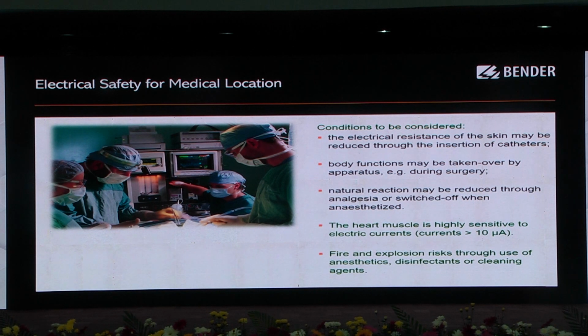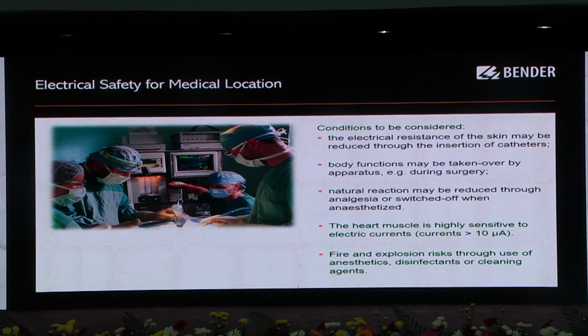it is in the IEC standard 60364-7-710, and our Indian standard is SP 30 2011, now upgraded in 2023. It is mandatory for group 2 locations. Earlier, for group 2 locations, they used ELCB or RCCB, which is a grounded system. Now the standard says you have to use an unearthed system inside the OT, ICU and premature baby room. It is mandatory. Wherever group 0 and group 1 locations are there, we provide a residual current monitoring system.